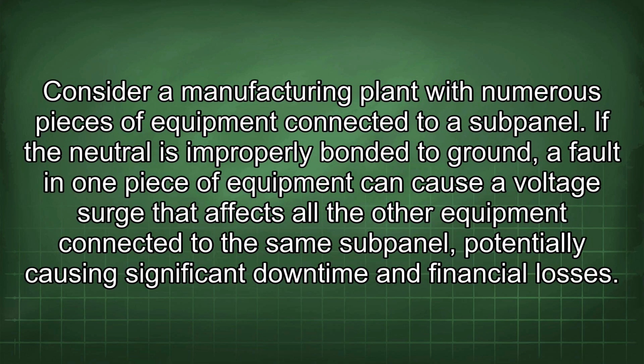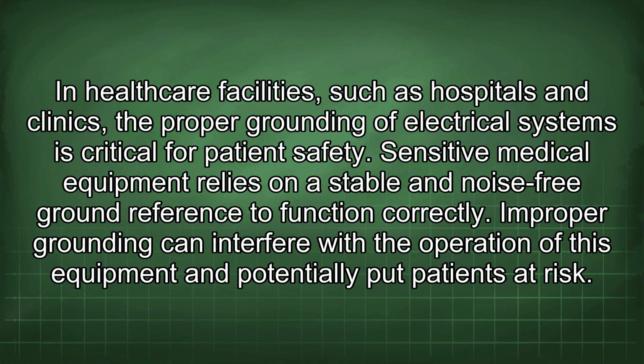Consider a manufacturing plant with numerous pieces of equipment connected to a subpanel. If the neutral is improperly bonded to ground, a fault in one piece of equipment can cause a voltage surge that affects all the other equipment connected to the same subpanel, potentially causing significant downtime and financial losses. In healthcare facilities, such as hospitals and clinics, the proper grounding of electrical systems is critical for patient safety. Sensitive medical equipment relies on a stable and noise-free ground reference to function correctly. Improper grounding can interfere with the operation of this equipment and potentially put the patients at risk.